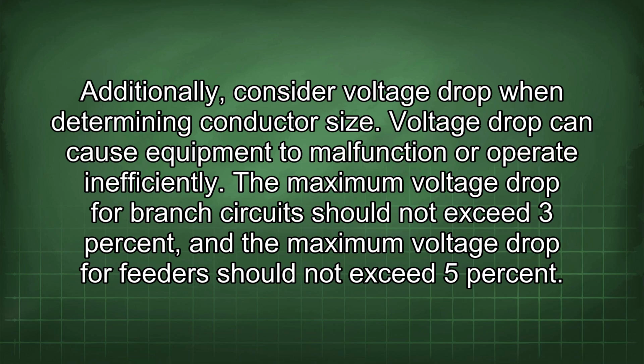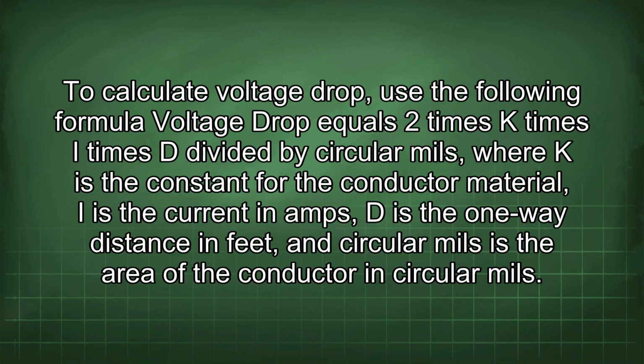The maximum voltage drop for branch circuits should not exceed 3%, and the maximum voltage drop for feeders should not exceed 5%. To calculate voltage drop, use the following formula: voltage drop equals 2 times K times I times D divided by circular mils, where K is the constant for the conductor material, I is the current in amps, D is the one-way distance in feet, and circular mils is the area of the conductor in circular mils.